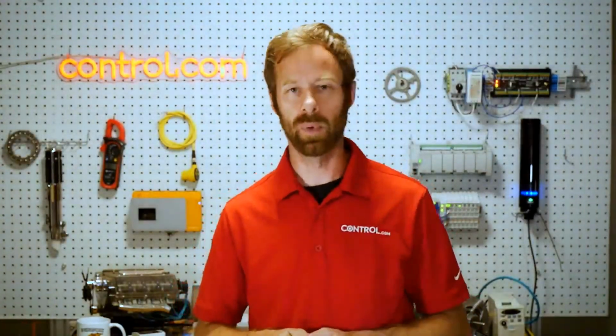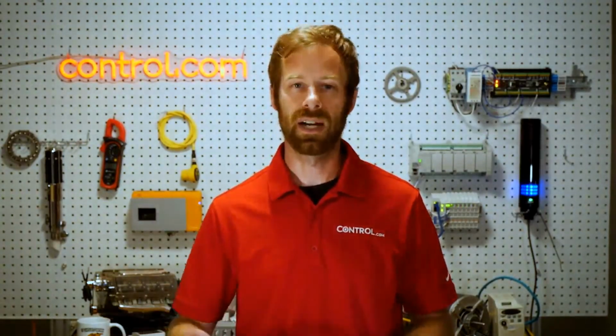The software side can also be a little bit more complicated because with analog and digital inputs, the only thing we need to worry about is the value of the tag in the PLC. It will be either a 1 or a 0 for discrete, or it'll be an integer value for analog.